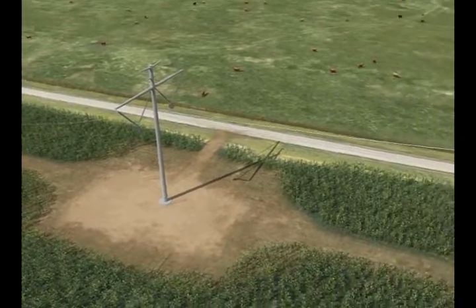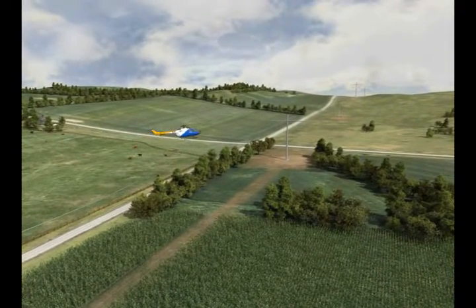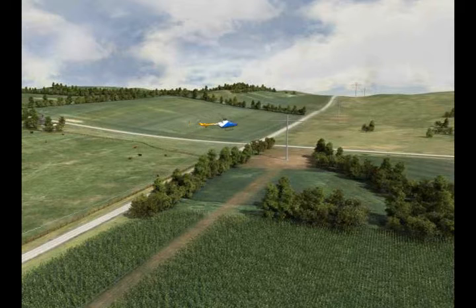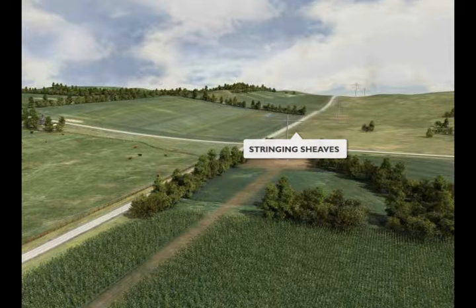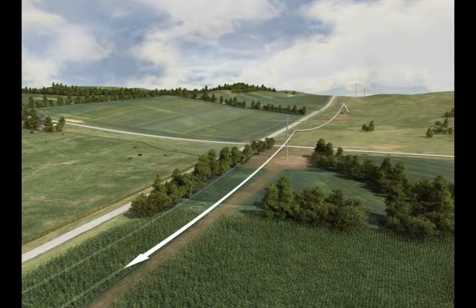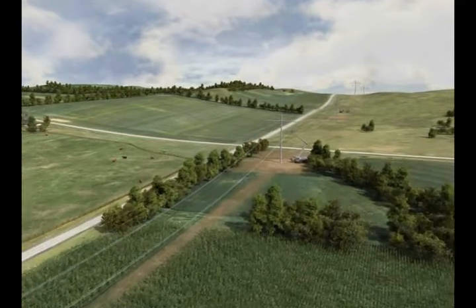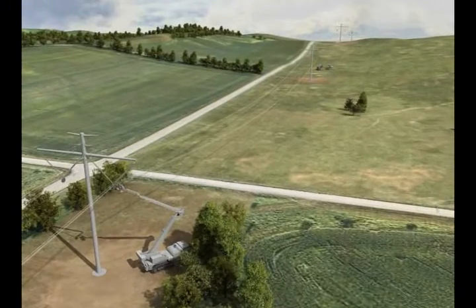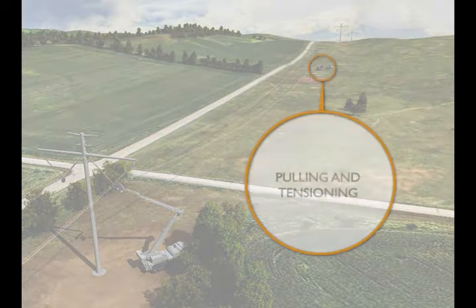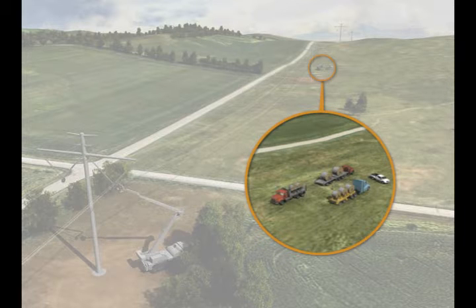After the structures are in place, crews will use specialized pulling equipment to install the conductors, ground wires, and any fiber optic cable. This process begins by first stringing pilot lines through the stringing sheaves on the structures. The pilot lines will be used to pull a stronger, larger diameter line attached to the conductors and ground wires. This process is repeated until the ground wires and conductors are pulled through all of the sheaves. Once the lines are in place, the pulling and tensioning equipment will maintain tension on the lines while they are fastened to the structures.